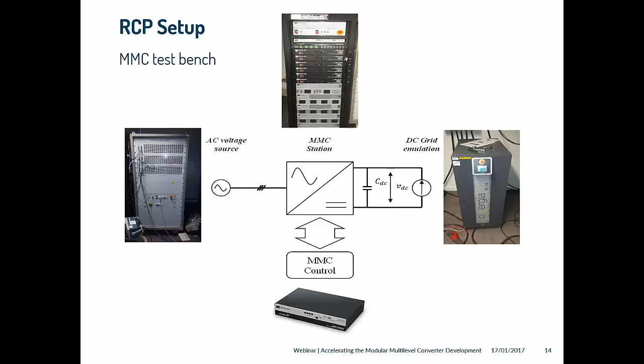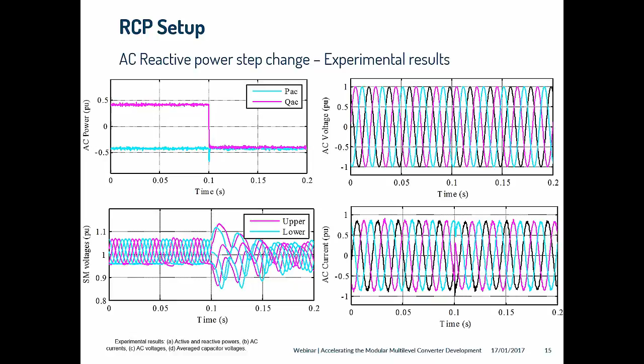It's an AC reactive power step change that occurs at 0.1 second. We see the AC power going from 0.4 PU to minus 0.4 PU, and we see the effects of this power step change on the average capacitor voltages of the different arms. We also see the effect on the AC current, which shows a sudden change in phase at the time of the step change.